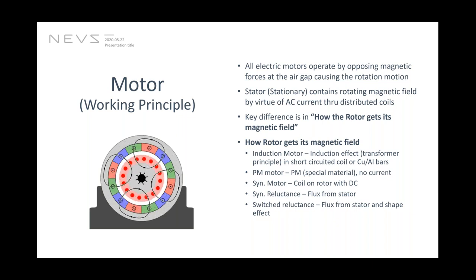So as I introduced different rotor types in the previous slide, in the induction motor, it is the transformer effect which induces some voltage: the rotating magnetic field induces some voltage in the rotor coils, rotor bars, and in turn current will circulate in the shorted rotor bars, and then it will produce the field in the rotor. In the permanent magnet motor, the rotor gets a field from a special material, permanent magnets, as the name implies. The synchronous motor is a very conventional one, still used in railways.